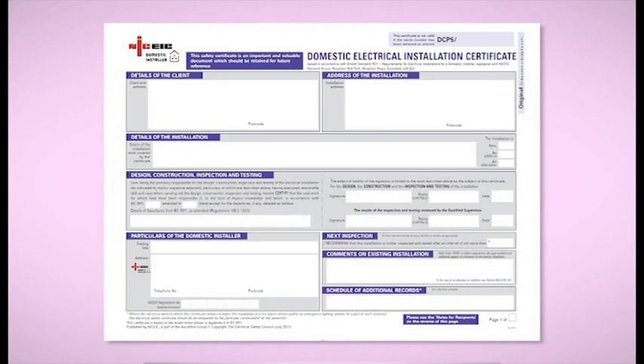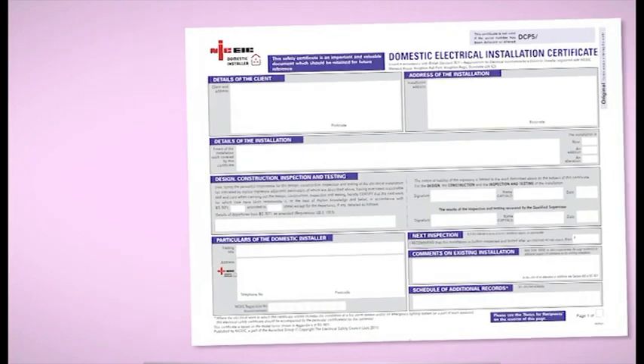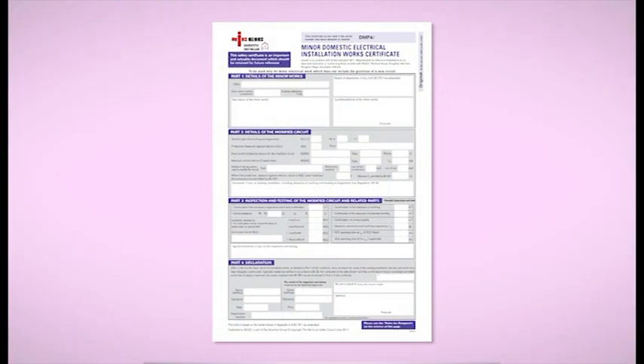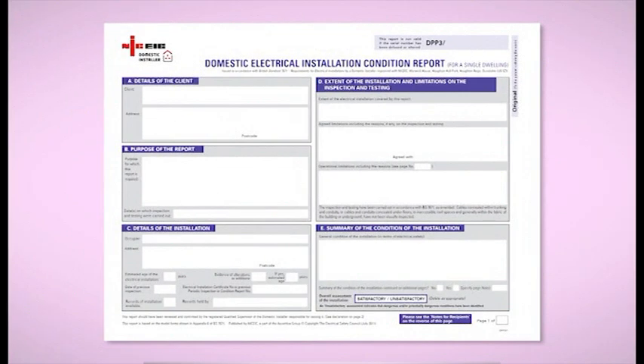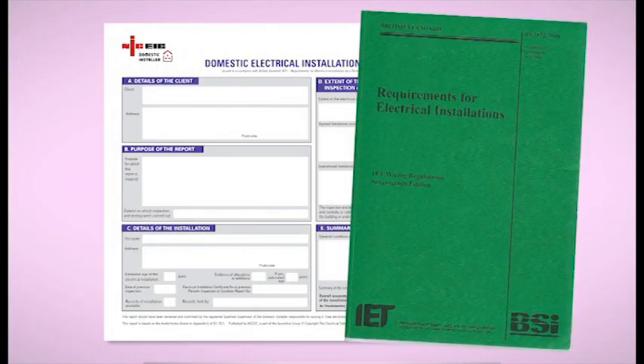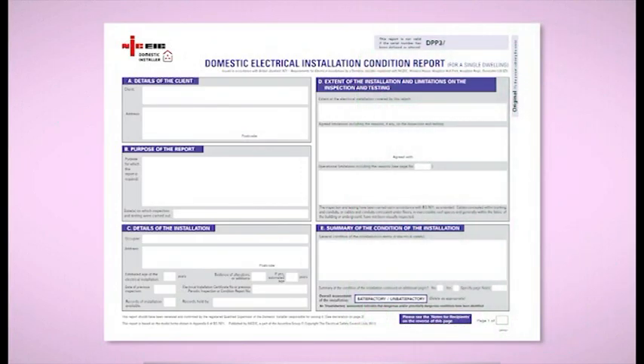Upon completion of a new installation or alterations or additions to an existing installation, the appropriate certification must be issued. For new installations, rewires, or the provision of any new circuit, this will be an electrical installation certificate. For an alteration or addition to an existing circuit, it will be a minor electrical installation work certificate. For reporting on the condition of an existing installation, an electrical installation condition report must be used. This was a major change introduced with Amendment No. 1 of the 17th edition and replaced the periodic inspection report as the form to be used for periodic inspection and testing. All of these documents can be produced in any durable medium, including written or electronic media, as long as the authenticity and integrity of originals and copies can be verified by a reliable process or method.